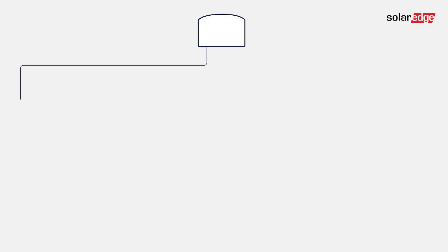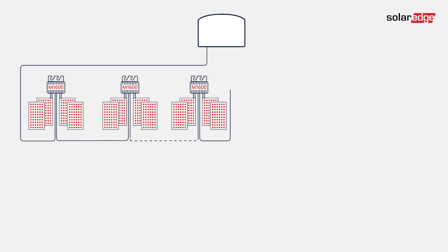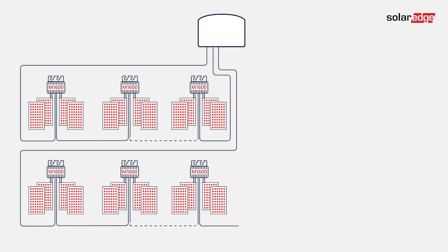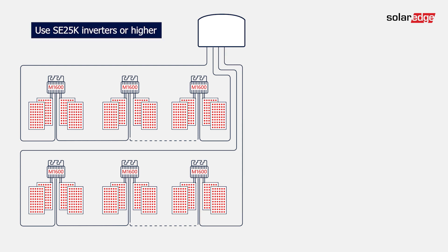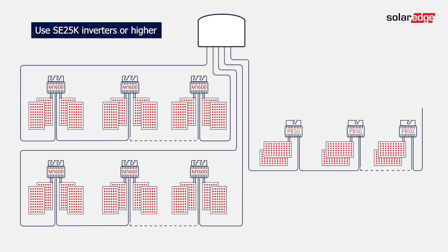Unlike other SolarEdge commercial power optimizers, which can be mixed and matched on the same string, the M1600 can only be installed with other M1600 units in the same string. It is not supported to connect another string which doesn't include any M1600s to the same inverter.